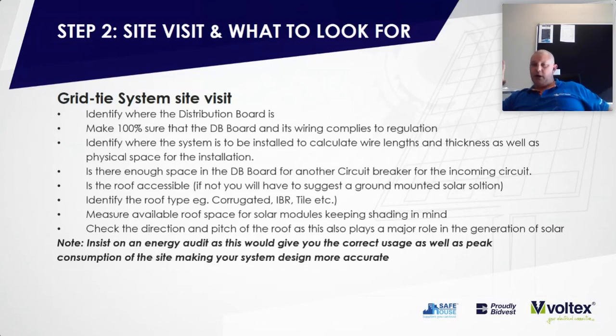There will be a circuit breaker allocated to the unit in its own separate distribution board, but as an added measure, we add another circuit breaker into the main board, or alternatively put a surface mount box next to the main board. If the system is not installed in close proximity of the distribution board, you would like to have access from inside the house, where the DB board is, to easily switch off the system in the event of something going wrong.